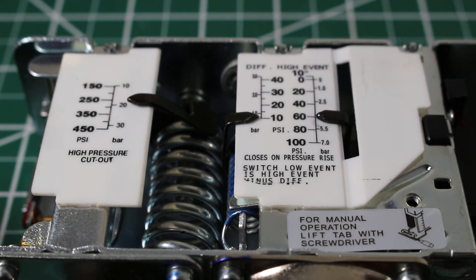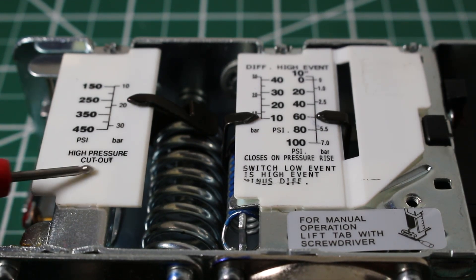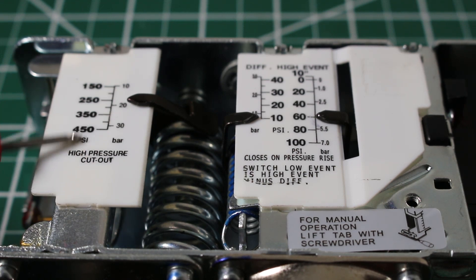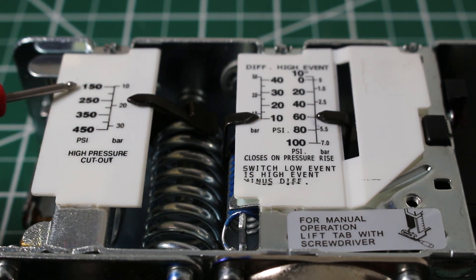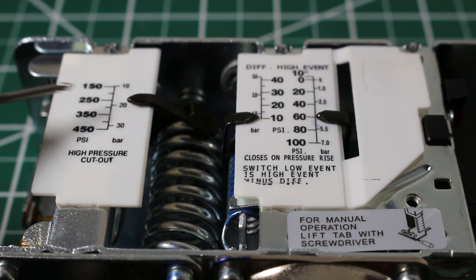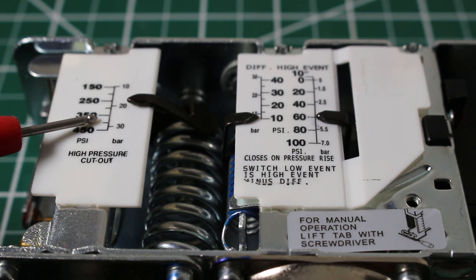Alright, let's start with the left side. As you can see, it says high pressure cutout, so this is our high pressure control. Here is our tab and we have a range from 150 to 450 and we just adjust our tab to the pressure we want our system to shut down at if it ever reaches those pressures.